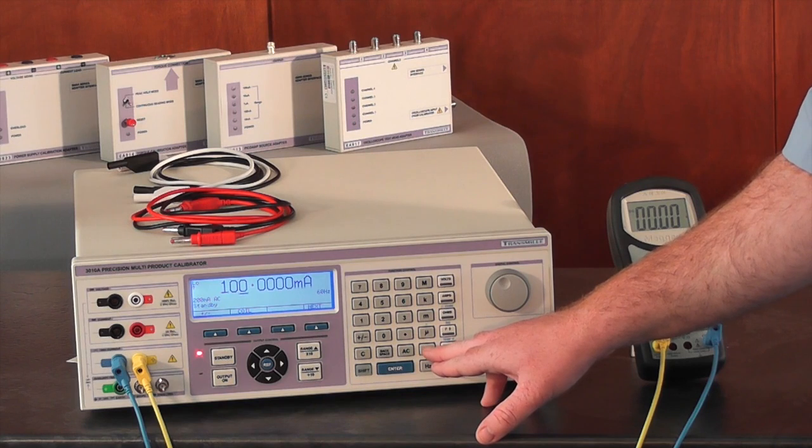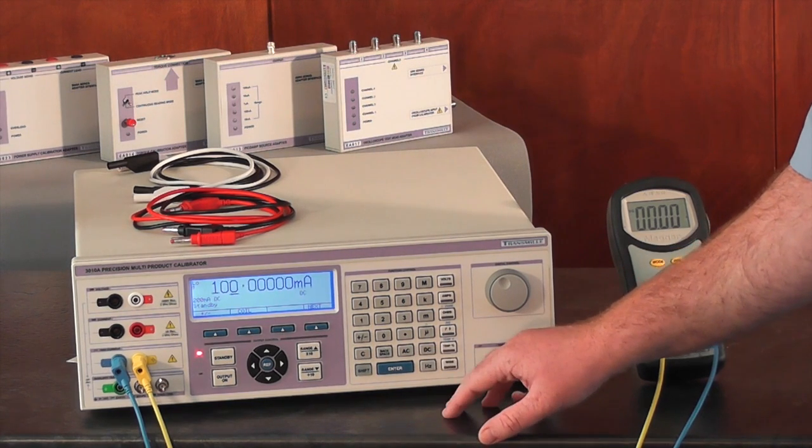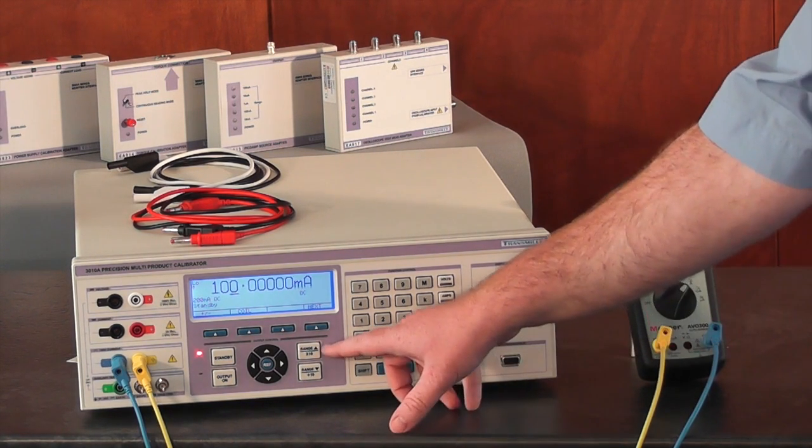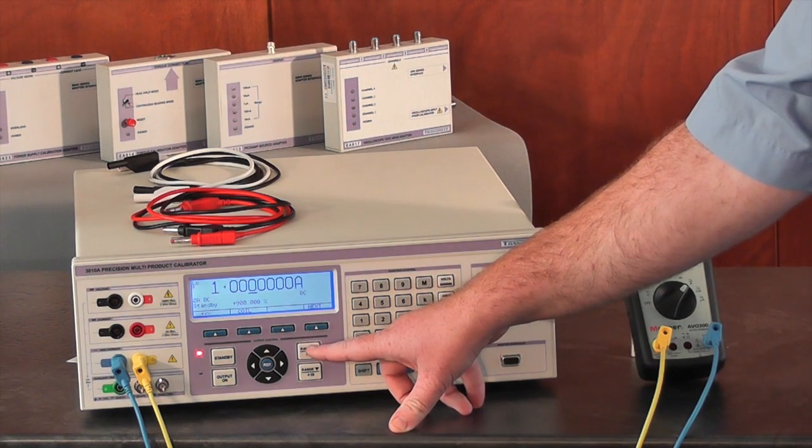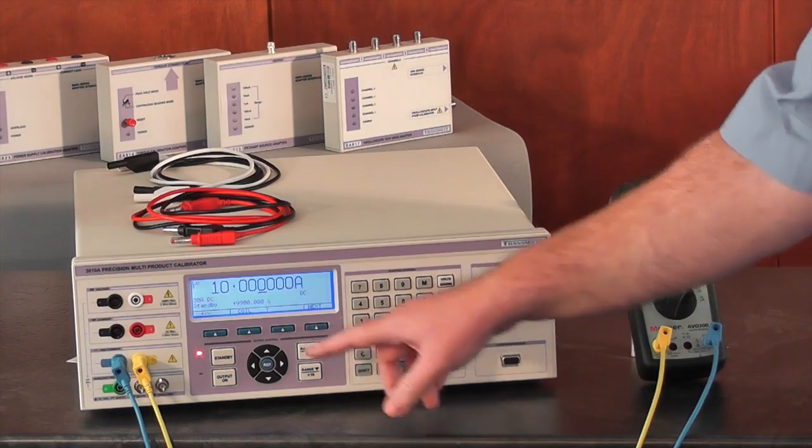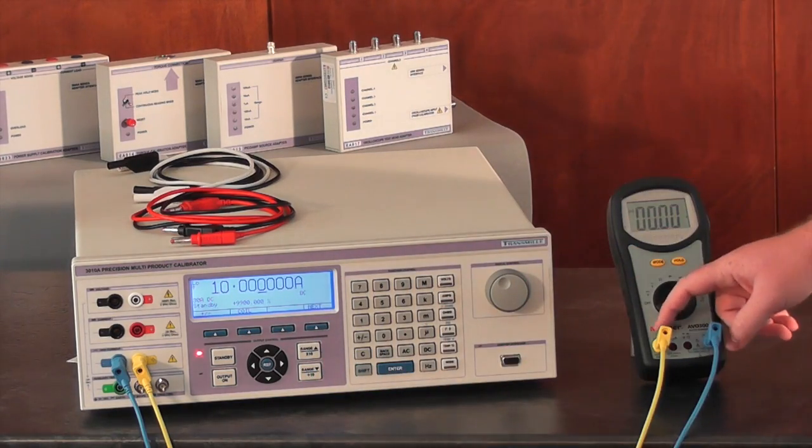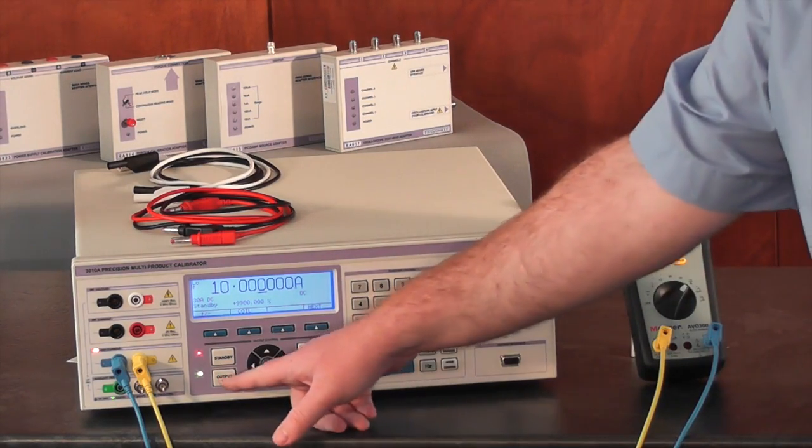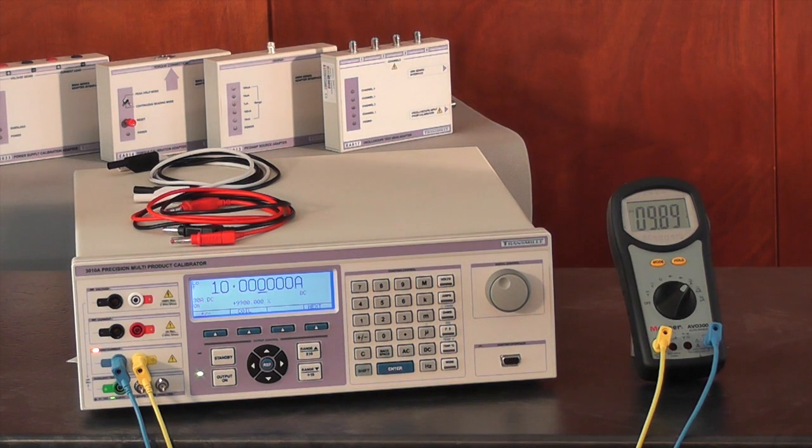We will switch the calibrator back to DC mode and use the range up keys to set a value of 10 amps. After checking the connections are correct, we will press output on. We can now take a recording of the indicated value from the multimeter.